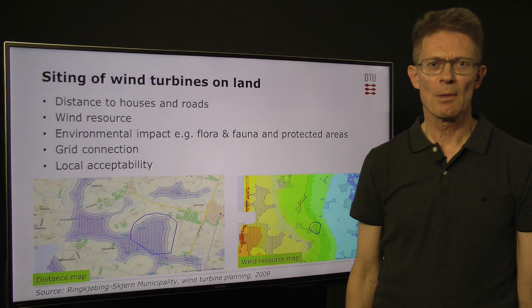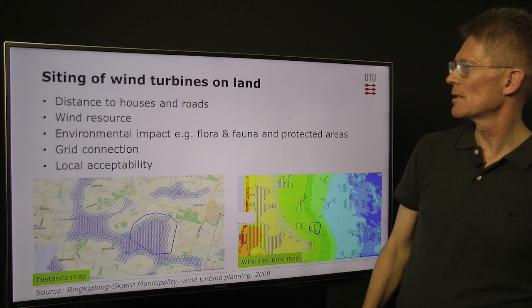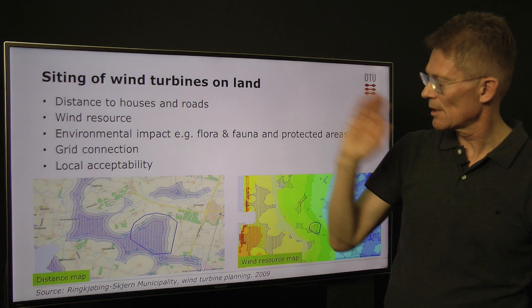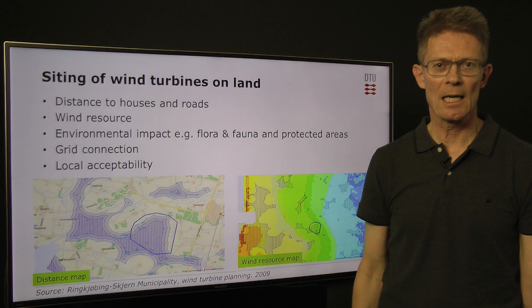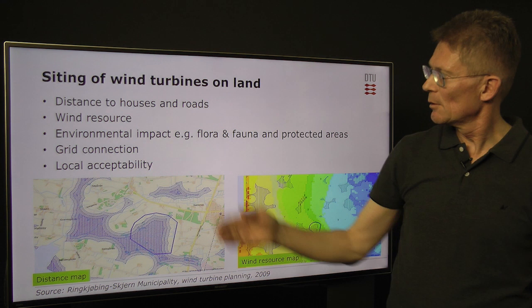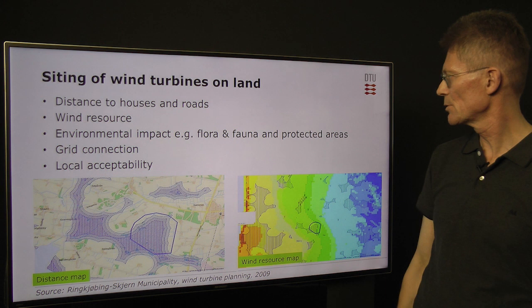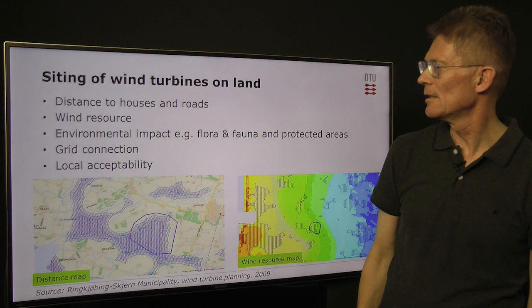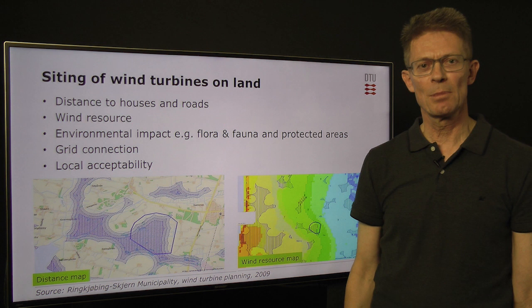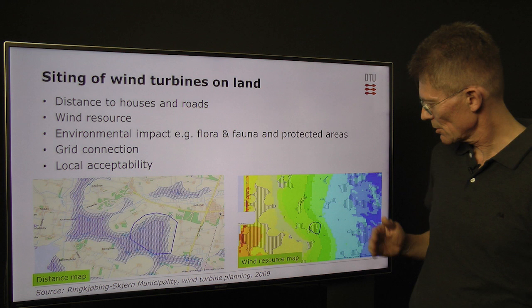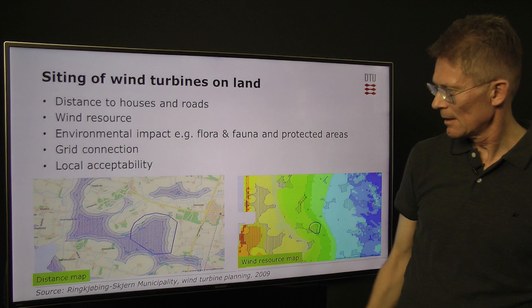When we do siting of wind turbines on land, there are a number of issues to consider. The distance to houses and roads is very important — in Denmark the nearest house must be at least four times the total height of the wind turbine. The wind resource is also important, as that is the fuel of our wind farm. Environmental impact — for instance, impact on flora and fauna — must be considered, and we also need to respect protected areas. The distance to the nearest grid connection is really important, and finally, local acceptability by the people living there is also of great importance.